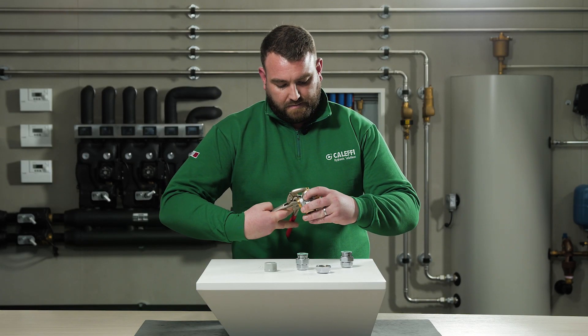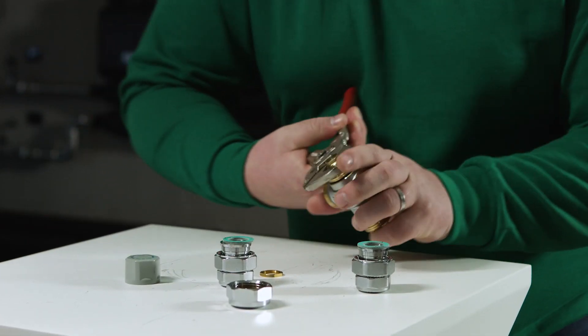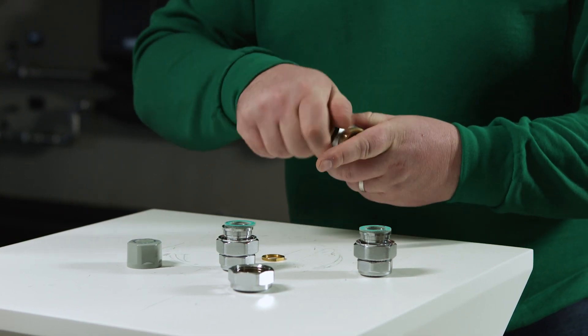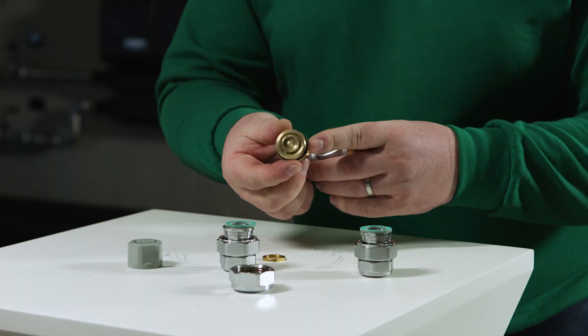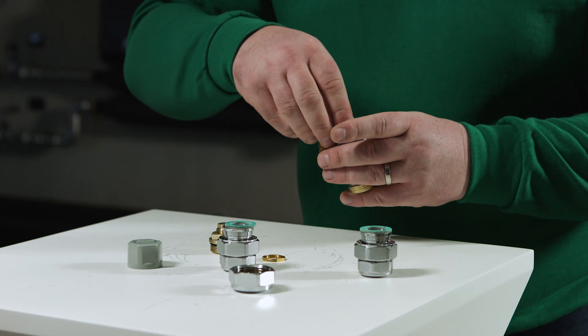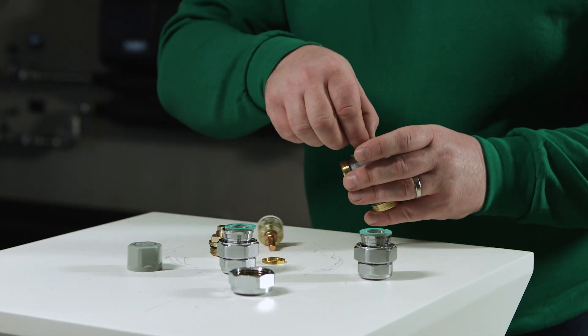The thermostatic mixing valve mixes hot and cold water at the inlet so as to maintain the mixed water at a constant set temperature at the outlet. A thermostatic element is fully immersed in the mixed water flow. It contracts or expands, moving an obturator which controls the passage of hot or cold water at the inlet. When the inlet temperature or pressure changes, the internal element automatically reacts to restore the set temperature at the outlet.